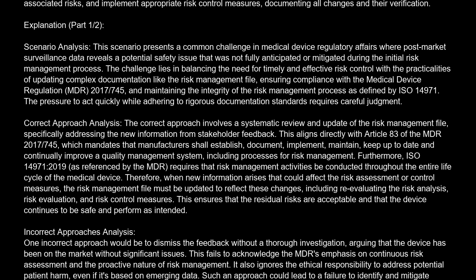Furthermore, ISO 14971:2019, as referenced by the MDR, requires that risk management activities be conducted throughout the entire life cycle of the medical device. Therefore, when new information arises that could affect the risk assessment or control measures, the risk management file must be updated to reflect these changes, including re-evaluating the risk analysis, risk evaluation, and risk control measures. This ensures that the residual risks are acceptable and that the device continues to be safe and perform as intended.